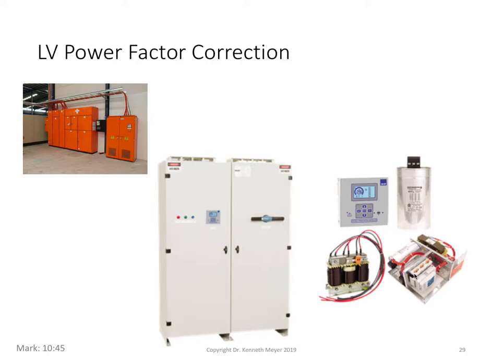So don't be tricked if you see a power factor correction unit. The power factor or the VARs created by the capacitors far outweigh the inductor that's there to slow up the inrush current.